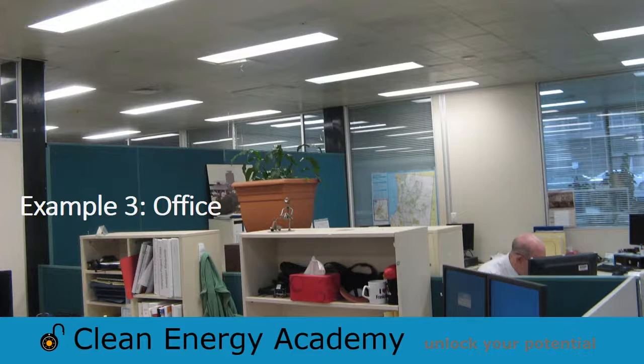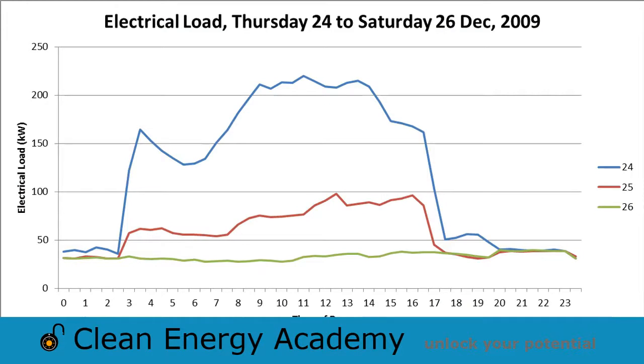From interval data, we can see the load profile here for the 3 days from the 24th of December, the 25th, Christmas Day, and the 26th of December. From this load profile, we can see that there is a lot of startup wastage. In other words, the air conditioning appears to be coming on very early in the morning, well before it's needed. Offices are normally occupied from around 7:30 or 8 o'clock in the morning, not in the early hours of the morning as this graph shows.